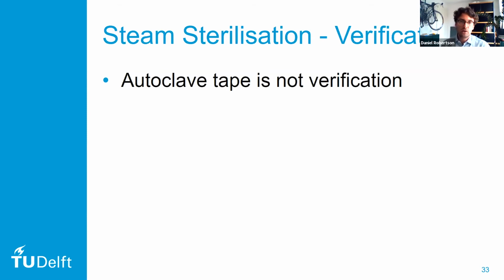What you see a lot is that we put a section of autoclave tape on the outside of the instrument packs. Unfortunately, this autoclave tape is not the same as showing that the instruments inside of the pack have become sterile. The problem is that as soon as this autoclave tape comes into contact with any steam, it will change color, but it doesn't show that the inside of the instruments or the inside of the packs have also become sterile. So the autoclave tape should only be used to show the difference between packs that have gone into the autoclave and packs that have not yet gone into the autoclave.